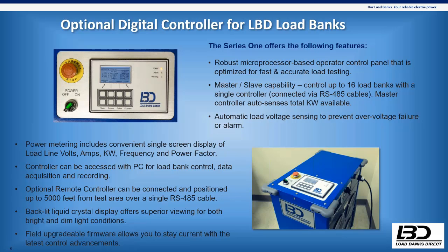I missed one of the biggest pros of this controller. It's all based on binary. So they all have 1, 2, 4, 8, 16, 32, and so on. That's how the steps are laid out. All of these units have 1 kW resolution, so you could take a 2.5 megawatt load bank and do a load test on a 10 megawatt generator, or a 10 kW generator if you wanted to. Not that anyone really wants to do that, because it's way too big of a load bank, but with this controller you definitely have that ability. That 1 kW resolution is a huge pro.